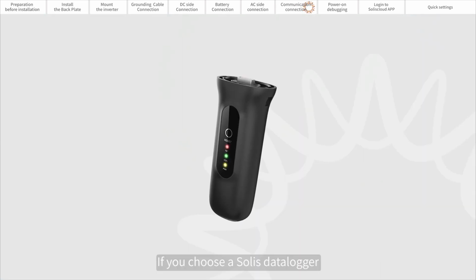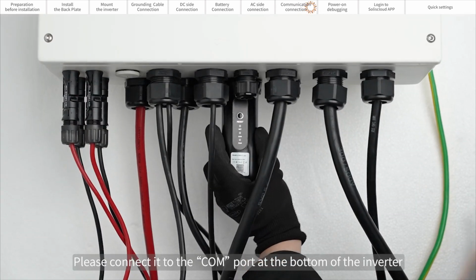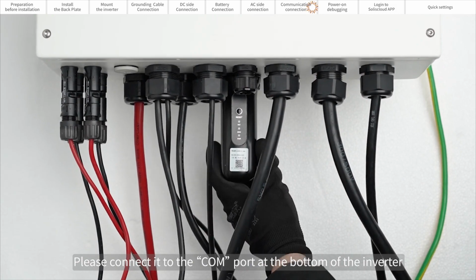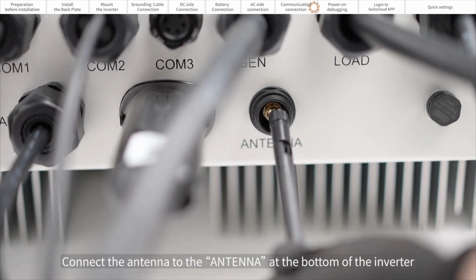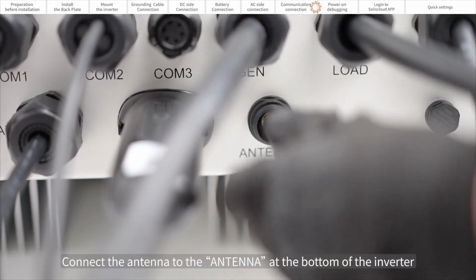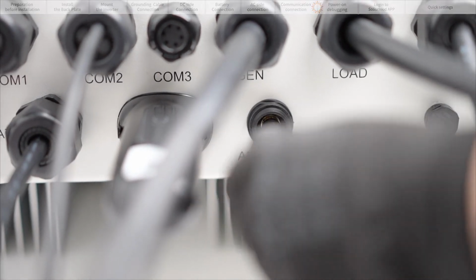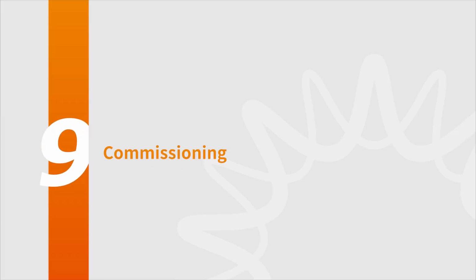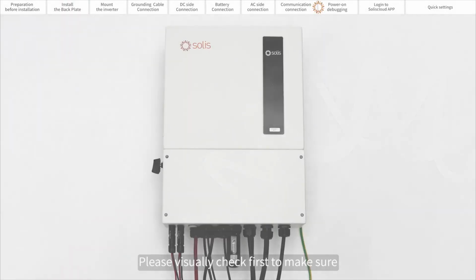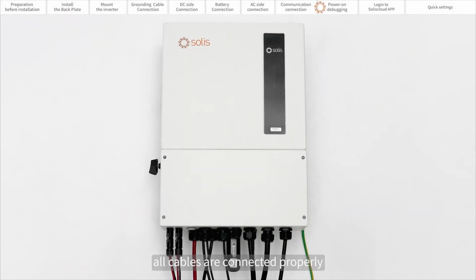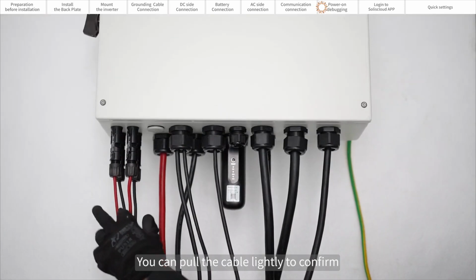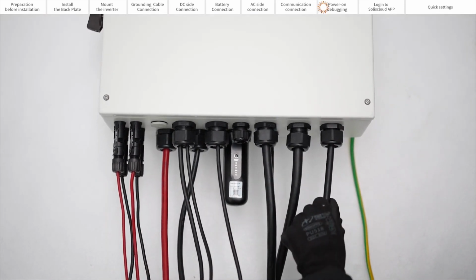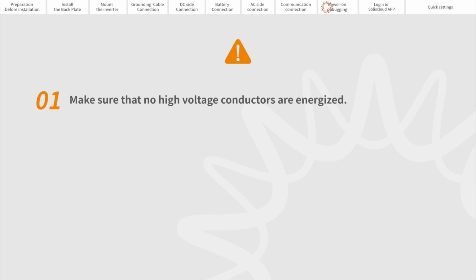If you choose a Solis data logger, please connect it to the COM port at the bottom of the inverter. Connect the antenna to the antenna port at the bottom of the inverter. Part 9. Commissioning. Please visually check first to make sure all cables are connected properly. You can pull the cables lightly to confirm. Ensure that no high voltage conductors are energized.